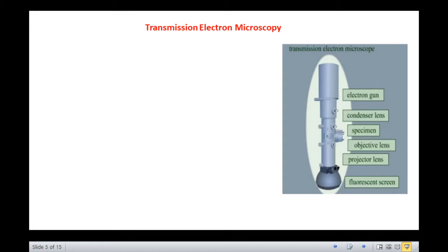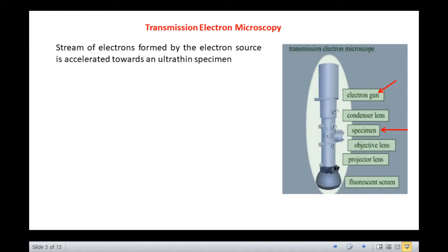Let us first have an overview of what exactly happens in a transmission electron microscope. A stream of electrons formed by the electron source is accelerated towards an ultra-thin specimen. This stream is confined and focused using metal apertures and magnetic lenses into a thin, concentrated, monochromatic beam. This beam is focused onto the sample using a magnetic lens.